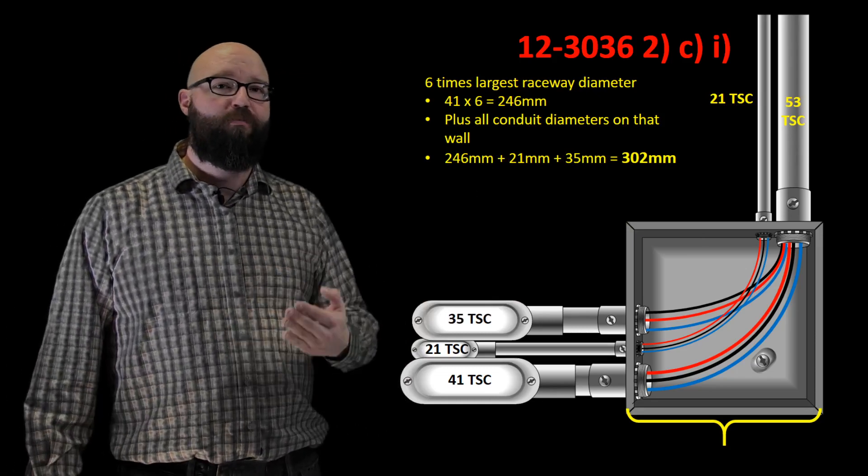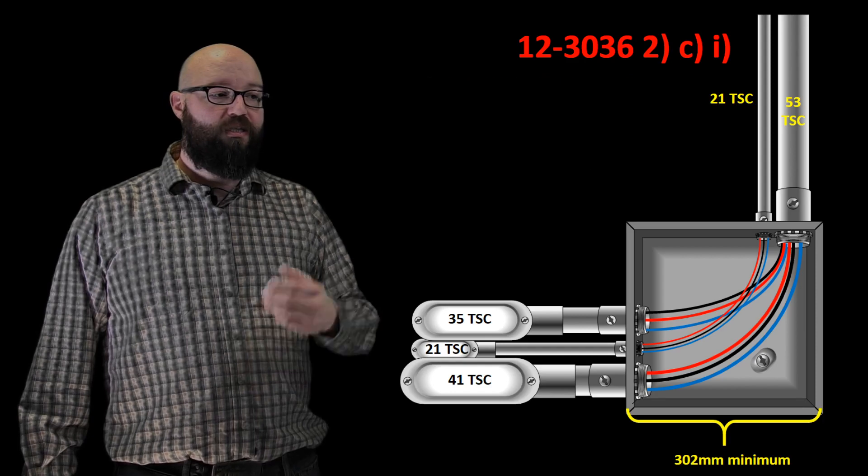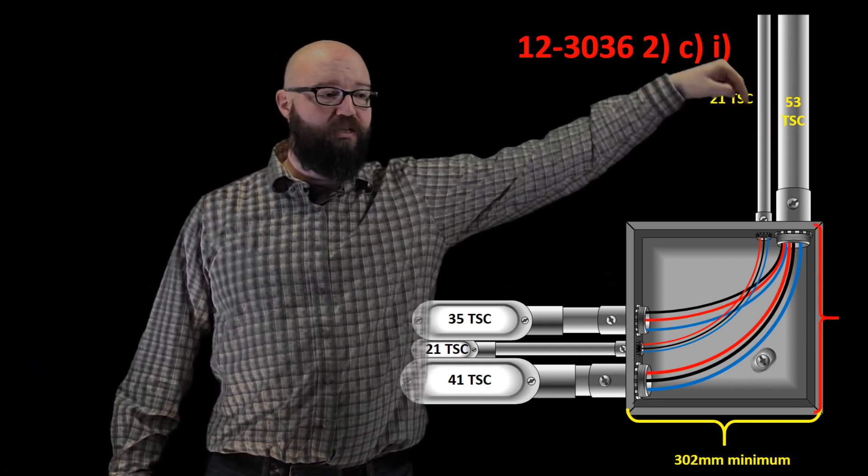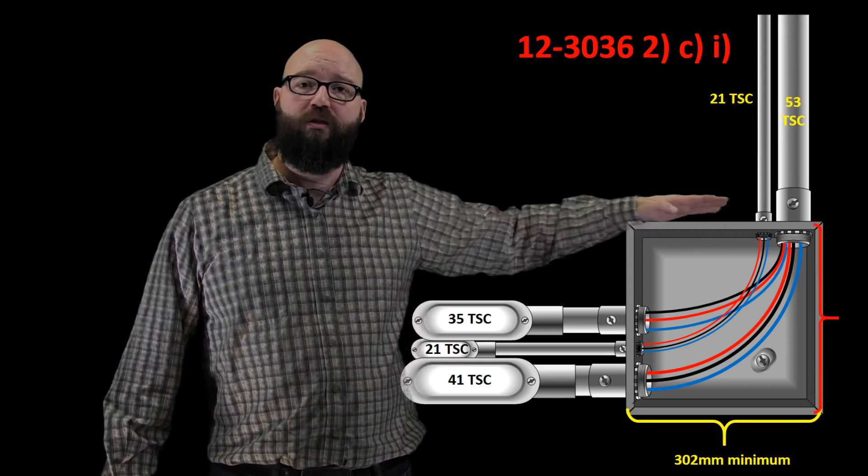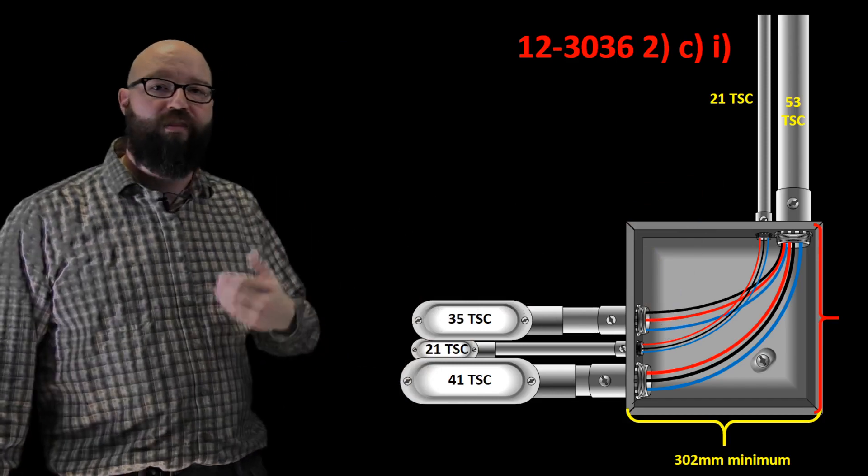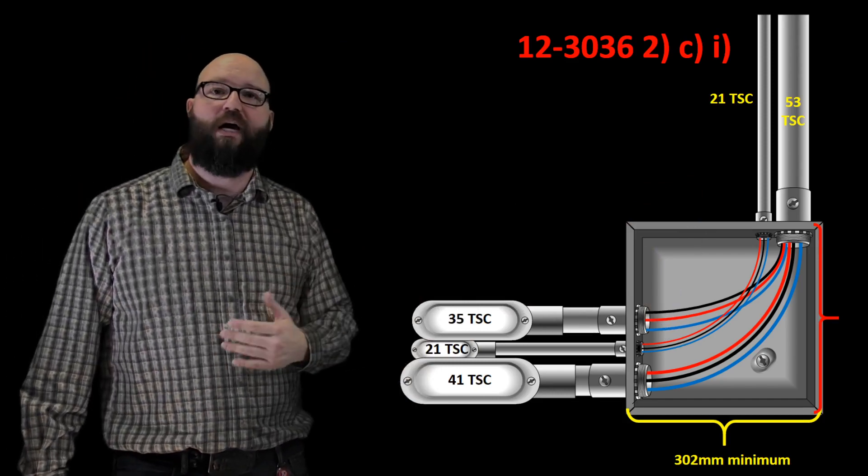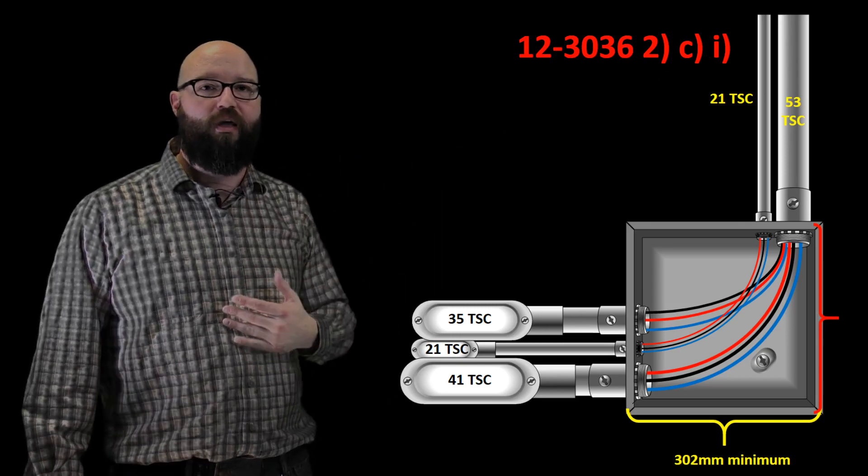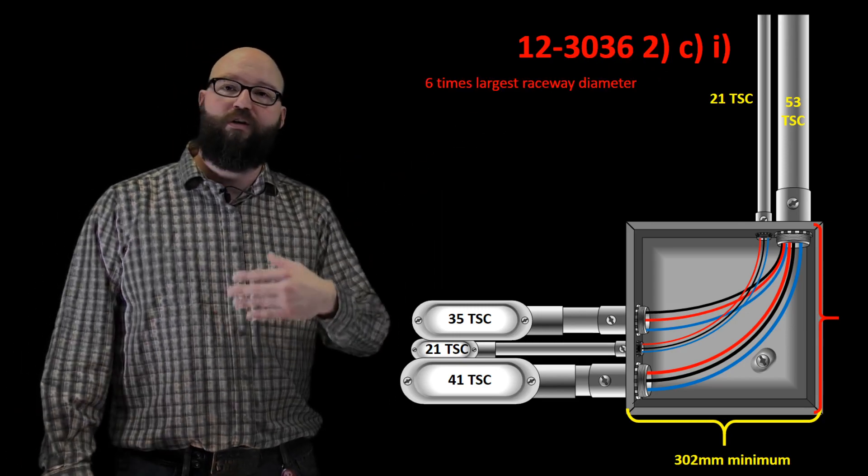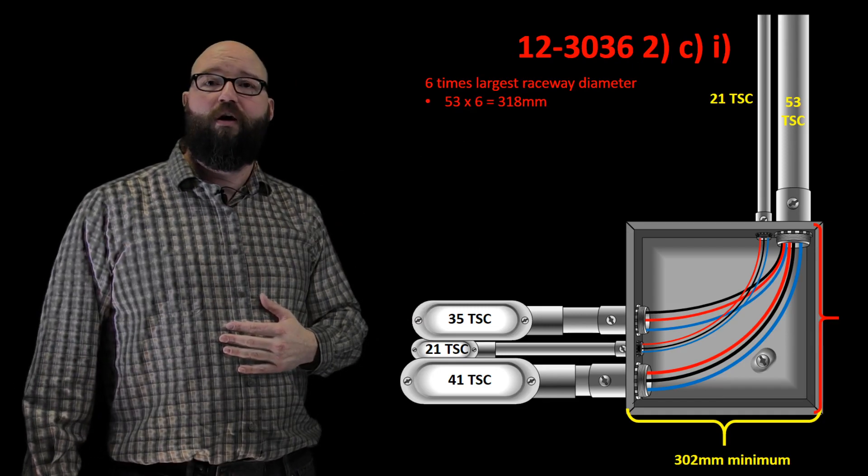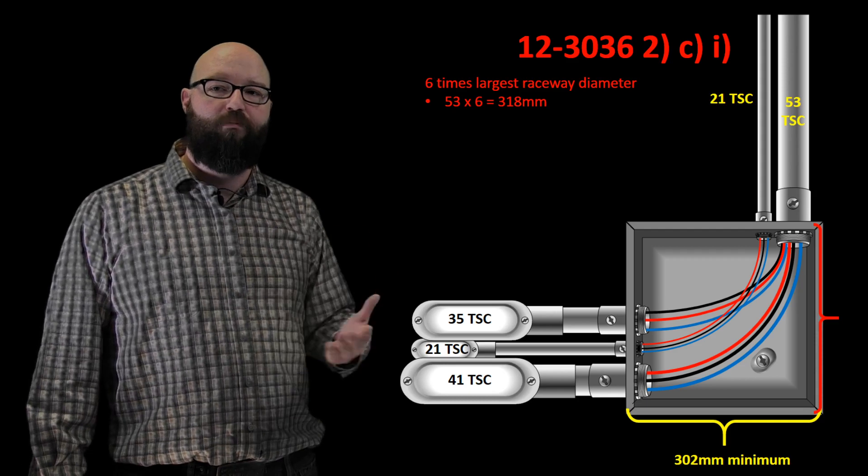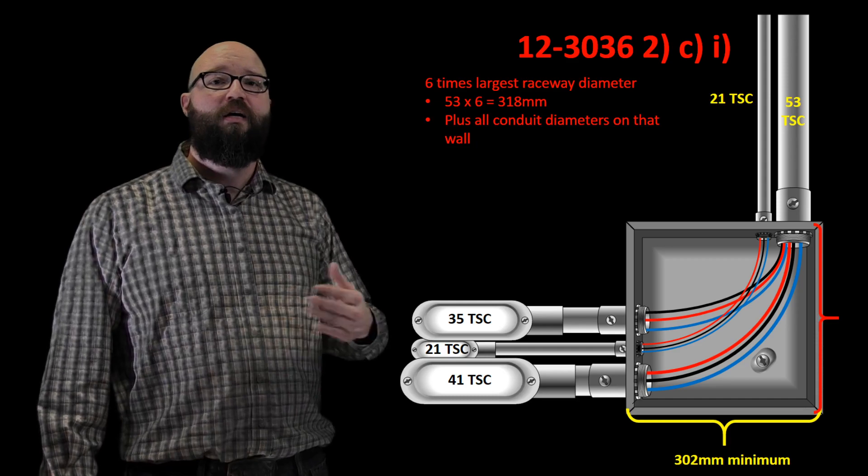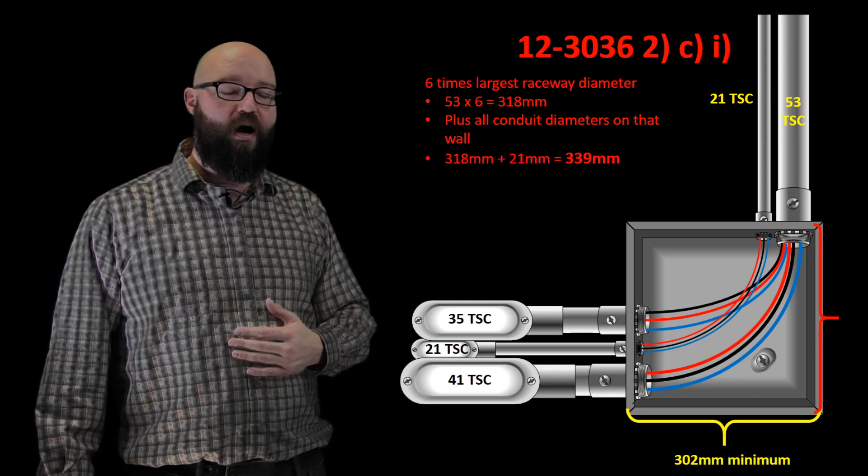We also have to take a look at the other dimension of the box as well. So in this case, if we take a look at the opposite, what we're looking at now, where these conductors enter, so this wall right here, what is the minimum distance to the opposite wall down there? That's what we're gonna take a look at next. We apply the exact same rule, it's just now we have our 21 trade size and our 53 trade size conduit that we're using in our calculation. So again, same thing, we're gonna use six times the largest trade size diameter, which in this case is actually 53. 53 times 6 gives us 318 plus that other 21 trade size conduit on there gives us a total on this now of 339.